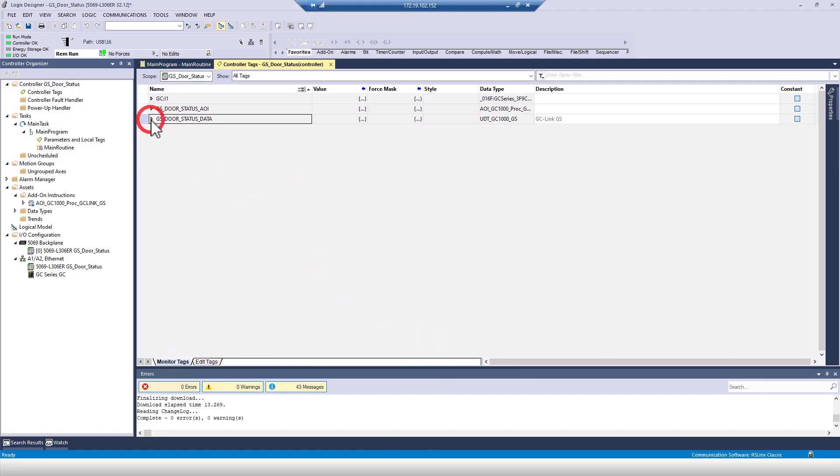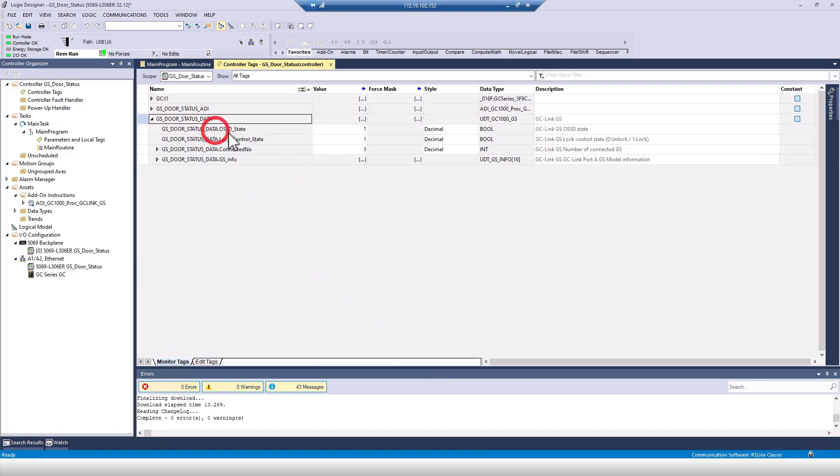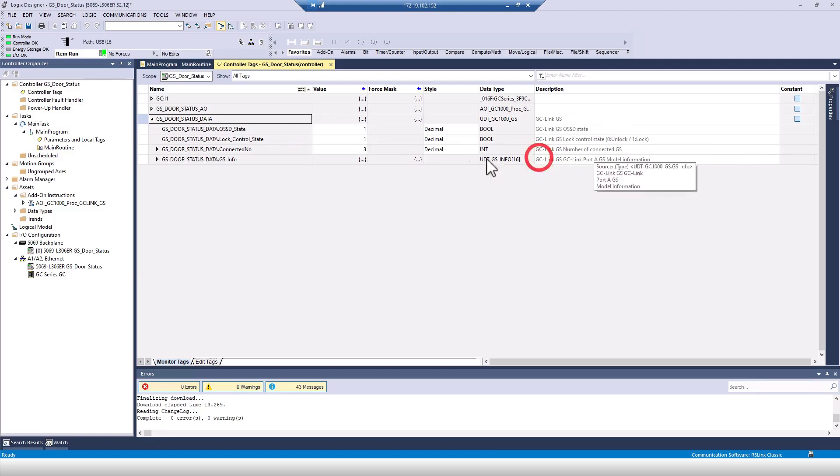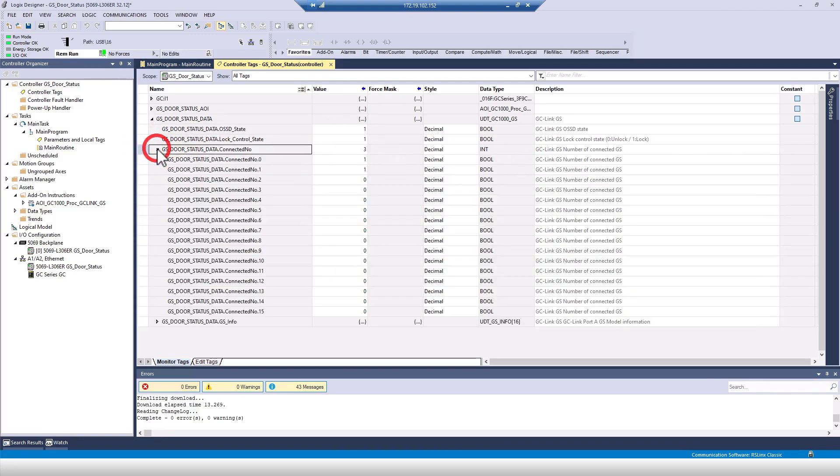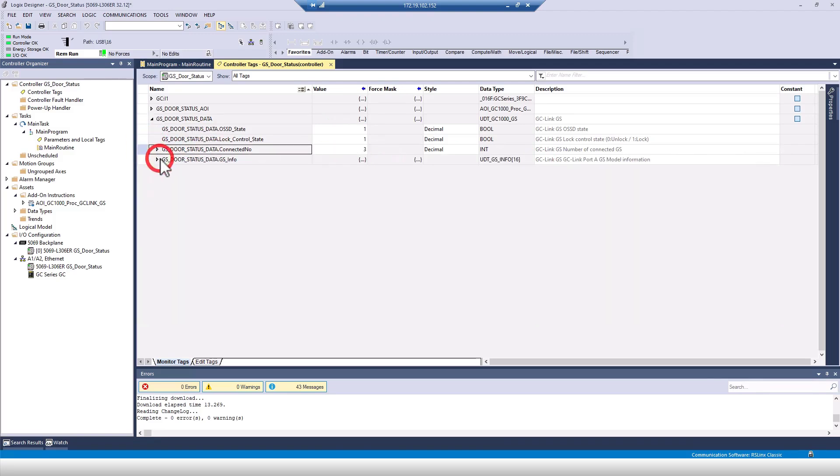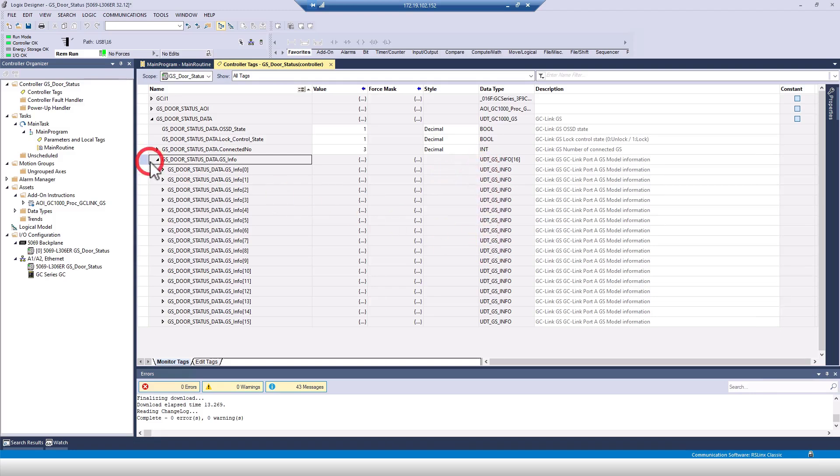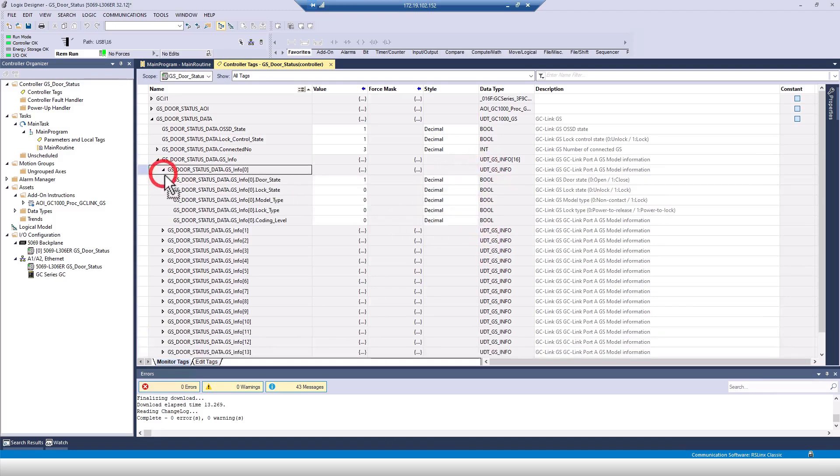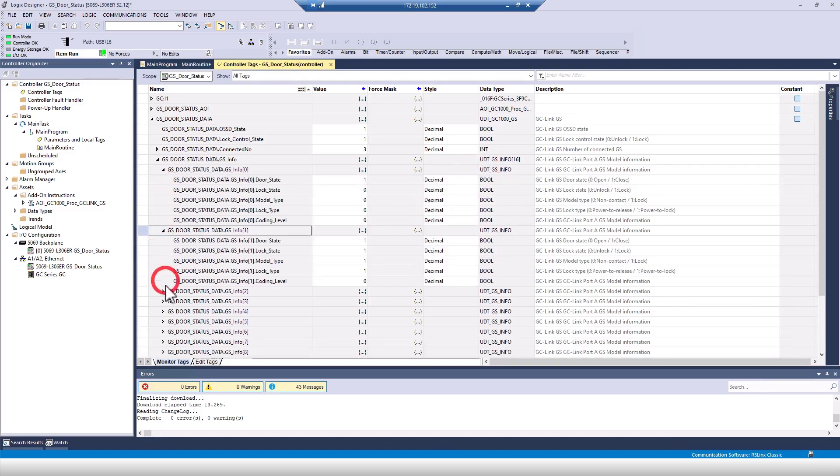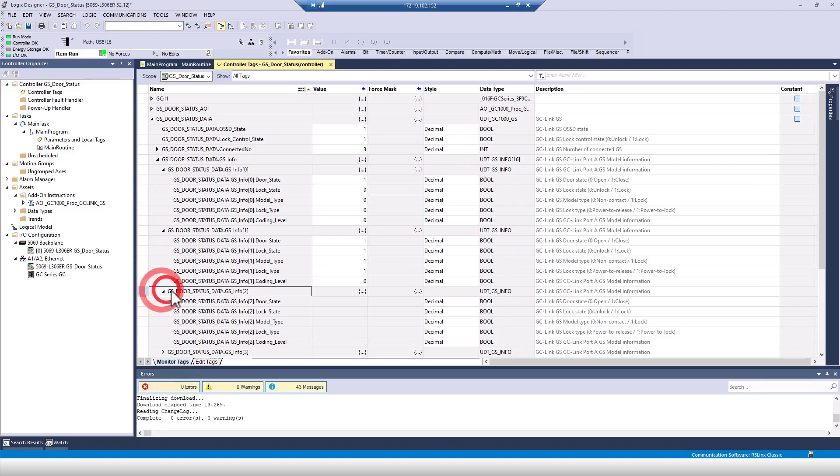Monitoring the tags, I can see that there's a lot of information that I can use, but what we'll turn our attention to is at the bottom, the gsinfo array. Here we can see an array of 16 UDTs. Each UDT corresponds to an interlock connected to the GC-Link port. Up to 16 interlocks can be connected in series, so 16 UDTs exist.